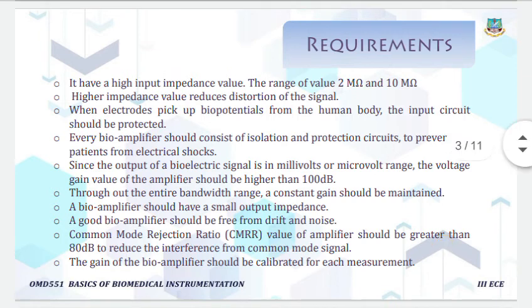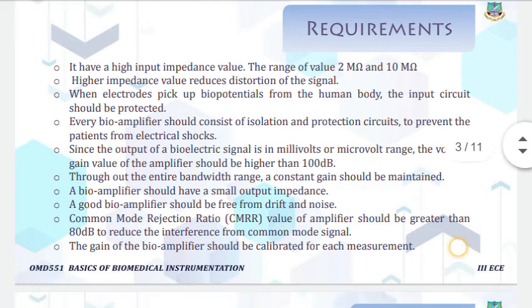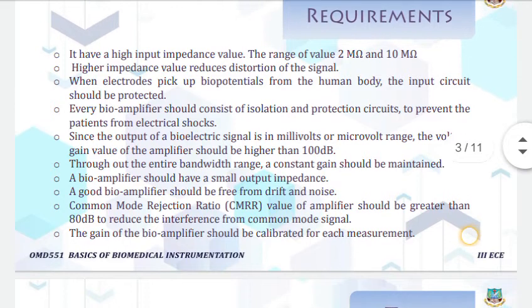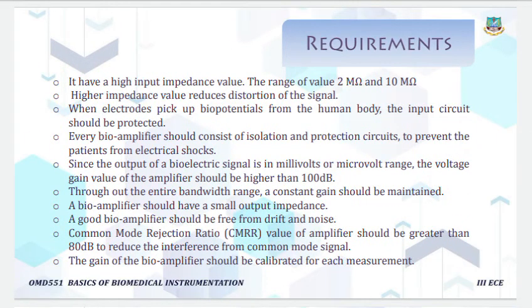Since the output electrical signal is in the millivolt or microvolt range, the voltage gain of the amplifier should be higher than 100 dB. Throughout the entire bandwidth range, a constant gain is maintained.